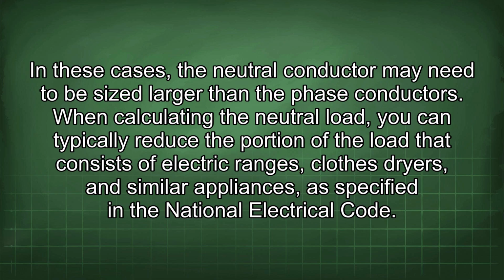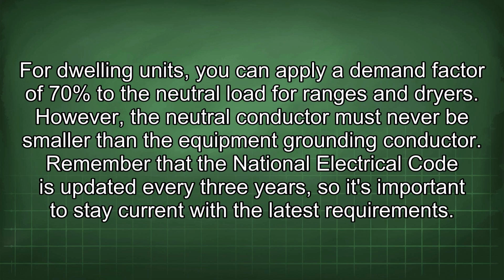When calculating the neutral load, you can typically reduce the portion of the load that consists of electric ranges, clothes dryers, and similar appliances as specified in the National Electrical Code. For dwelling units, you can apply a demand factor of 70% to the neutral load for ranges and dryers. However, the neutral conductor must never be smaller than the equipment grounding conductor.